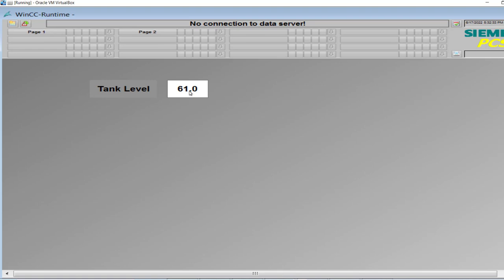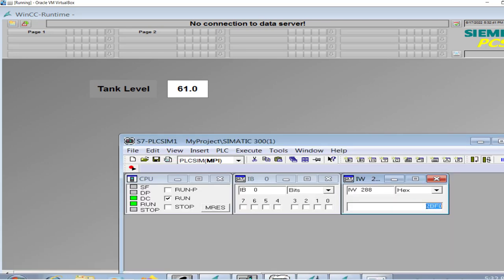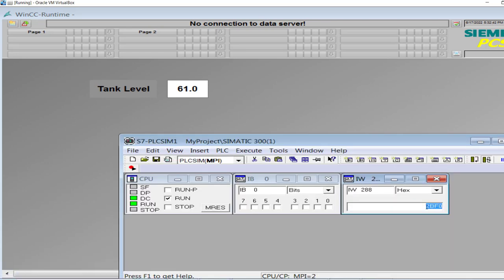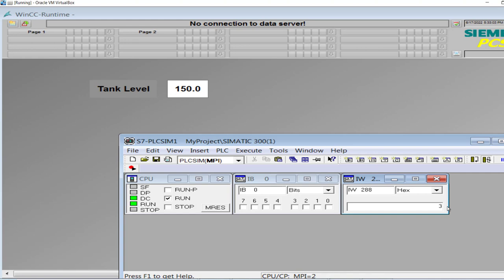61.0 is the actual decimal value of the sensor. That is the decimal representation of 4 to 20 milliampere coming from the sensor. If I change the value from the simulator to zero, it is 0.0. And the maximum value as we know is 6C00, and that is 150, which is the range of the sensor in this case. Anywhere in between would be linearly displayed on the HMI. 3F00 for example: 87.5.